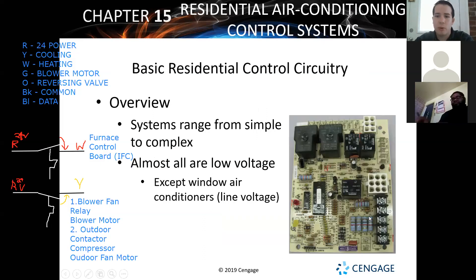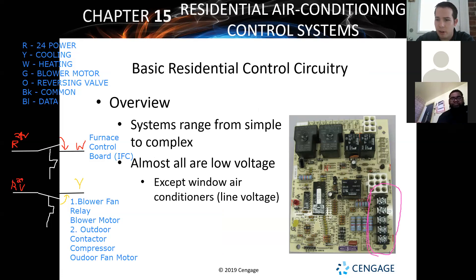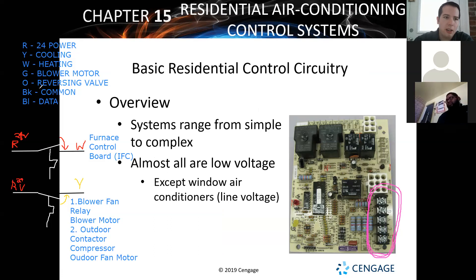Control boards are our most common thing we'll be seeing. If you look at this control board, you'll see a set of screw terminals. Each one — you unscrew it with your Phillips head, put a thermostat wire behind it. You can see: R, C, Y, G, and W. R is your power; C is your common, which can be either a black or a blue wire, just depends on how the person who wired it decided to do it that day.